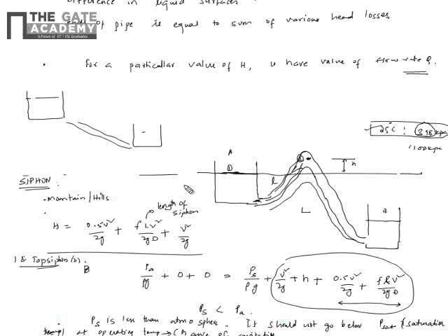If the pressure goes below the saturation pressure at operating temperature, the liquid cannot stay in equilibrium and converts into vapor. Those vapors collide with the walls and burst, leading to higher pressures and damaging the wall surface of the pipe. We don't want that case.